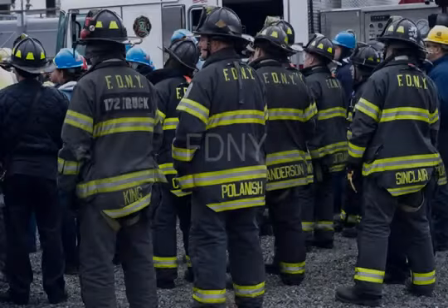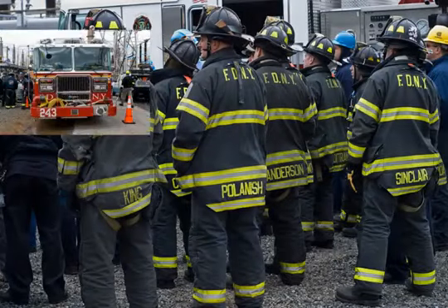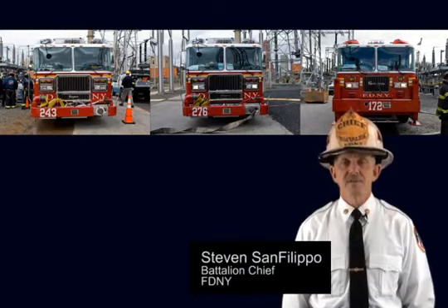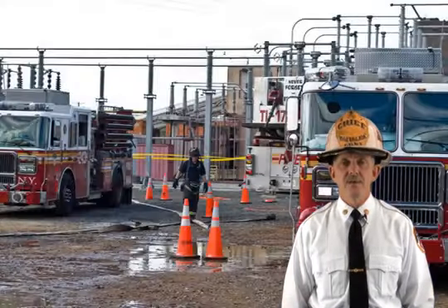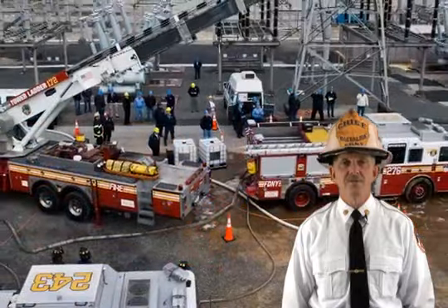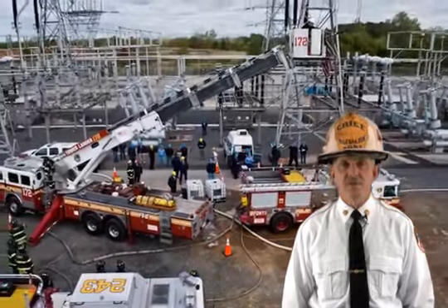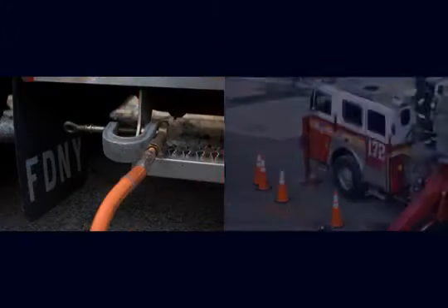For the Con Edison fire suppression test, the FDNY provided 2 pumpers and a tower ladder. Hello, my name is Battalion Chief Steven Sanfilippo. All 3 were used to apply F500 fire suppression agent to the live bus at Con Ed's high voltage station in Staten Island. All our equipment was grounded before any testing commenced.